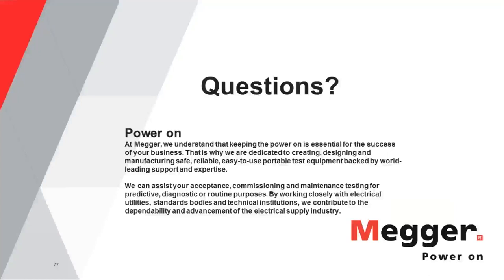And so, like I said on one of the earlier questions, these standards agencies that are nonprofit, independents, and so forth, they set the trends. They tend to be very conservative, but a lot of times they're the ones who are setting the trends and changing the rules. And I think IEEE's on the ball with this. The 5 gigohm value, of course, like all of these things, is somewhat arbitrary, but it's arbitrary in the right direction. And as a general rule, I would follow that. PIs are very reliable and a very good test when you're down into the megohm range and in the low gigs. But once you get up above that, the number itself becomes so overwhelming in importance that that's what you want to work with.